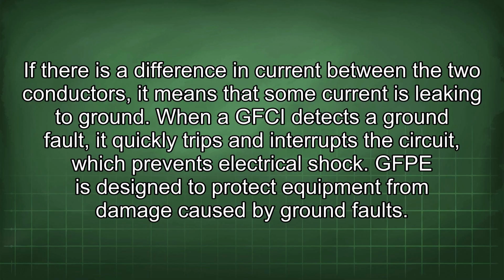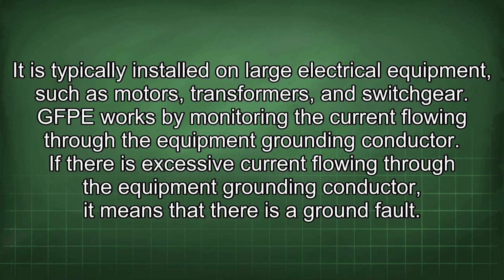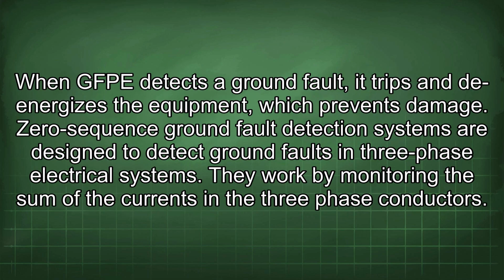GFP is designed to protect equipment from damage caused by ground faults. It is typically installed on large electrical equipment, such as motors, transformers, and switchgear. GFP works by monitoring the current flowing through the equipment grounding conductor. If there is excessive current flowing through the equipment grounding conductor, it means that there is a ground fault. When GFP detects a ground fault, it trips and de-energizes the equipment, which prevents damage.